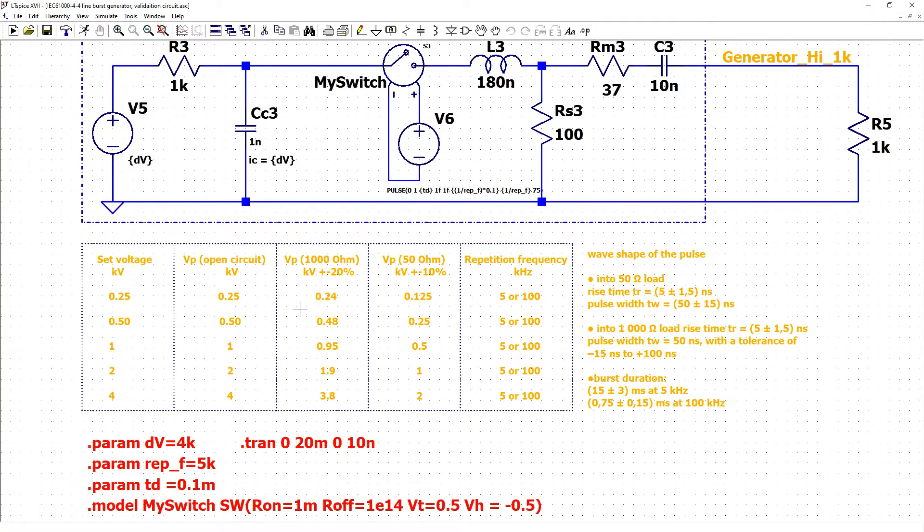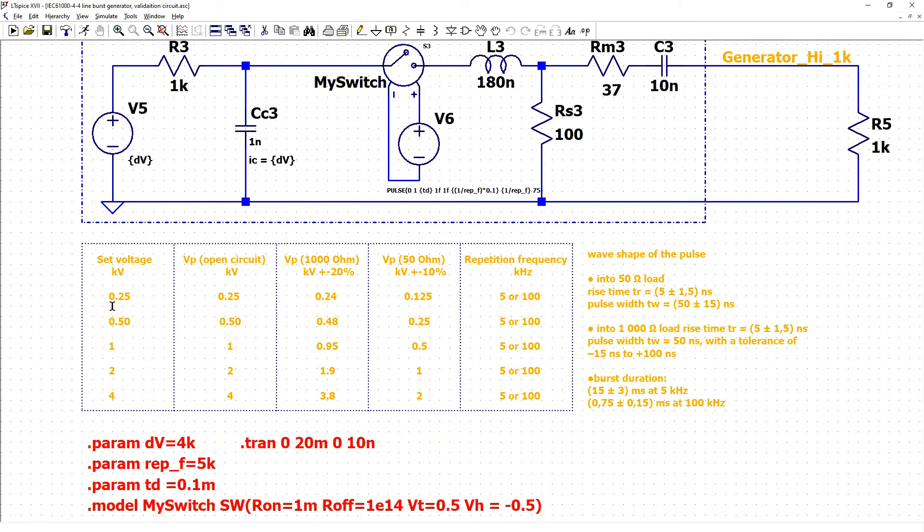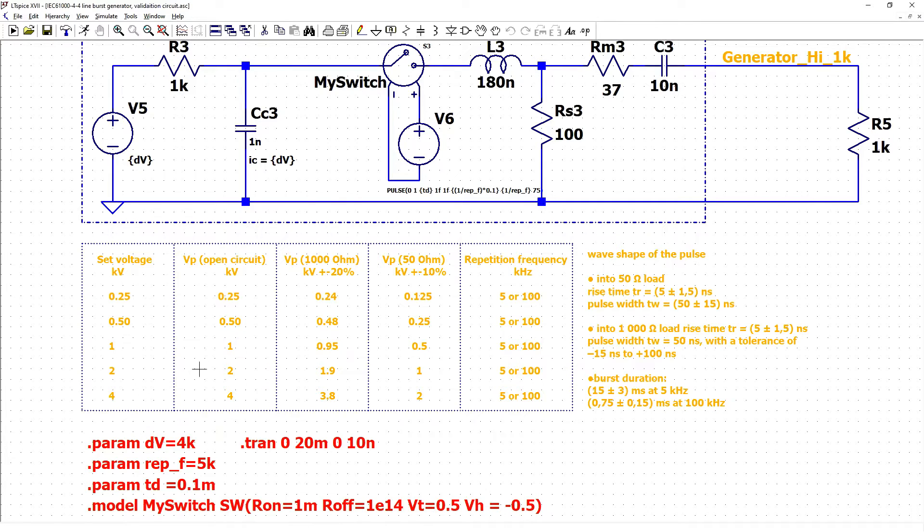We have requirements that when we set proper voltage from 250 volts to 4kV that depends on the standard and the device that will be tested, the open circuit values should be the same.